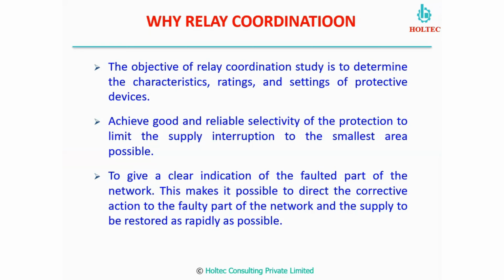Suppose one motor protection is operating, our total effort will be to check that particular motor for the fault. But if our LV switchboard incomer is tripping, then we don't know, as there are 50, 60, 70 motors connected to that device. So how can we identify the fault? Relay coordination will not only give us fast clearing of the fault and protection of the equipment, it will also pinpoint the correct position of the fault, so that we can take corrective action very fast and restore the equipment as early as possible.